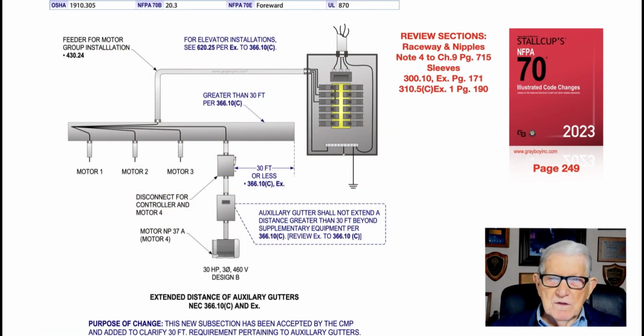Now, this illustration deals with extended distance of auxiliary gutters in accordance with NEC 366.10(C), an exception. Now, this rule used to be in the 2020 NEC. It's section 366.12, item number 2. And this was the problem, and was usually considered this way by the electrical industry. But notice the disconnect beneath the auxiliary gutter here. If it does not extend over 30 foot from the side of that disconnect to the end of that auxiliary gutter, it's still an auxiliary gutter.